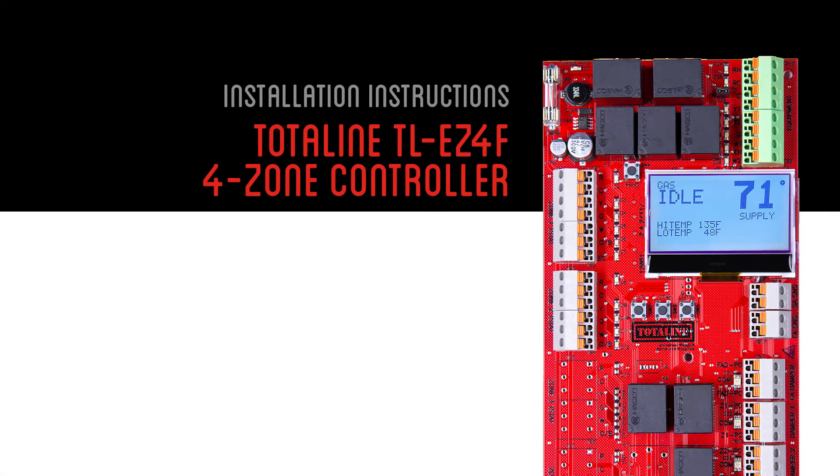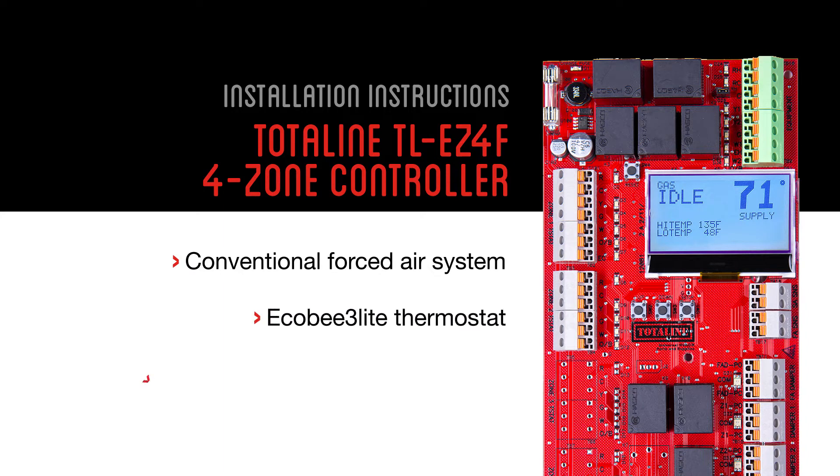Be sure to check the compatibility of all devices prior to installation and note that the supply air sensor is required for the system to operate. In this video, we're installing the Totaline TL-EZ4F four-zone controller to a conventional forced air system with an Ecobee3 lite thermostat and Totaline 8-inch power open, power close, three-wire dampers.